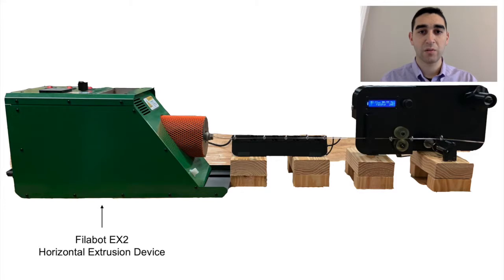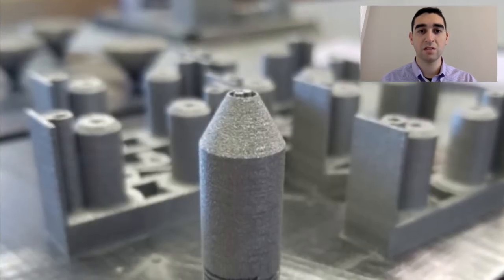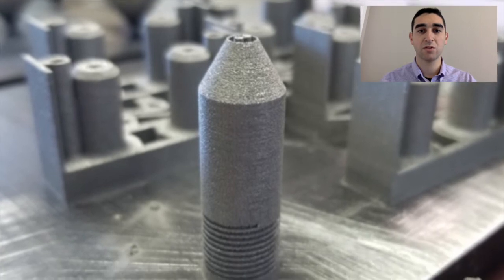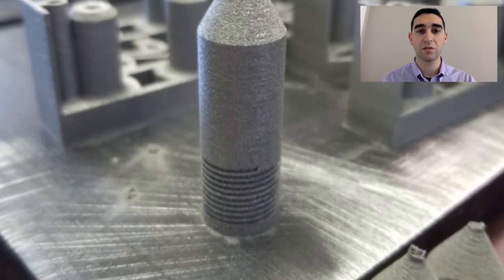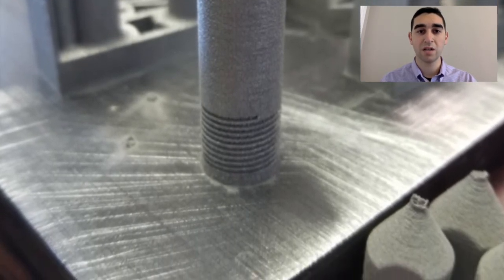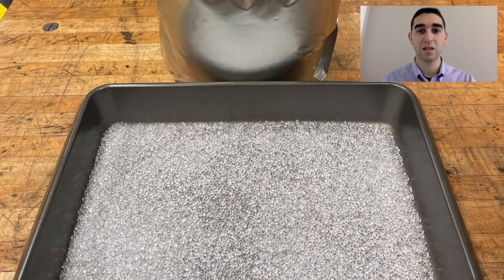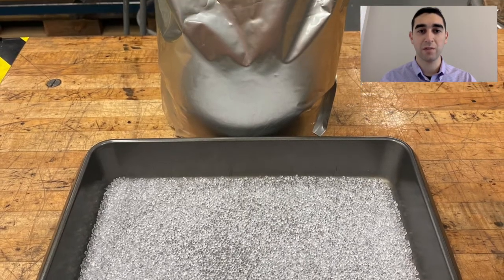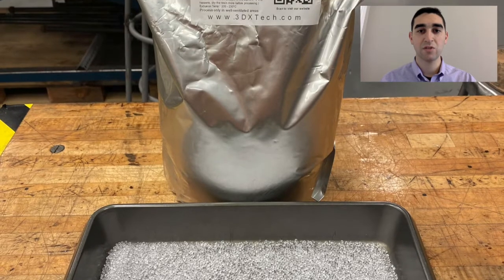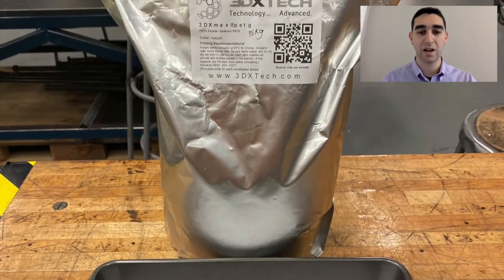We selected a refurbished Filabot EX2 paired with a Filafill spooler and air path cooler for our horizontal extrusion system because of its ability to meet each customer need. We decided to use stainless steel 316 for the custom extrusion nozzle material specifically for its powder availability, hardness, and heat resistance. Lastly, we selected PETG for the catheter body material because it exhibits a low temperature of extrusion, high rigidity, and high dielectric strength.